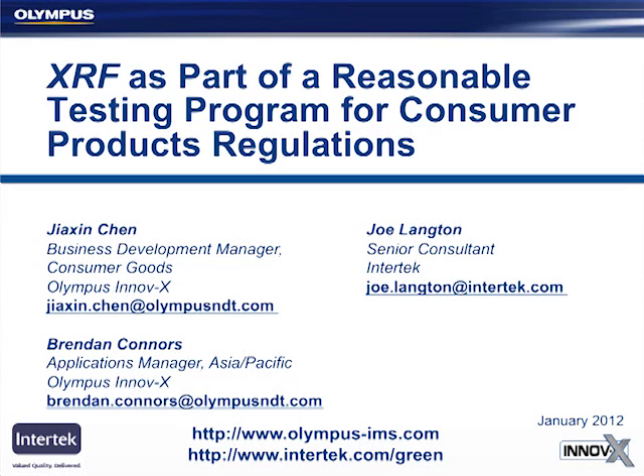Okay, for testing of stainless, nickel, and duplex alloy steels with high levels of chromium, what tube voltage is going to be preferred or better for that kind of testing? Of the options that I mentioned, 40, 45, or 50, that's the maximum spec for the tube voltage. It's not going to matter much for chromium analysis. The voltage spec is just the maximum on the tube, and the tube can always be run at lower voltages. This is something the user usually doesn't have control over. That's set up within the analyzer's software. But as far as the maximum tube voltage spec between the ones that I mentioned for chromium testing, it's not going to make much of a difference.